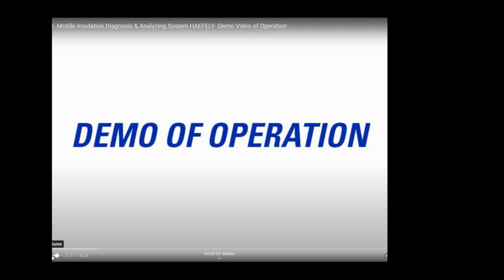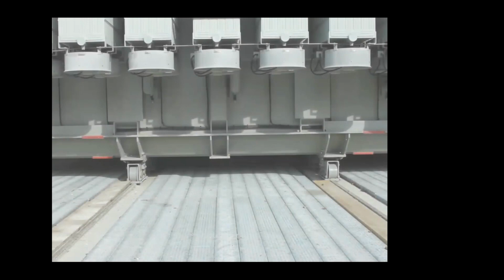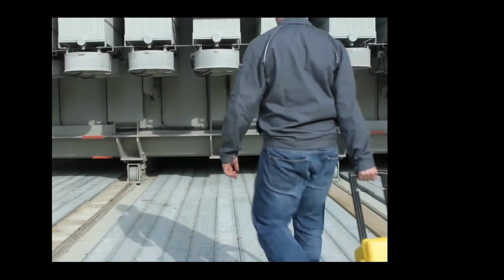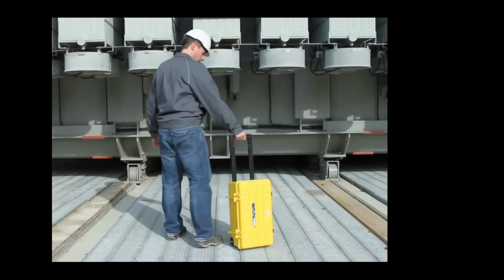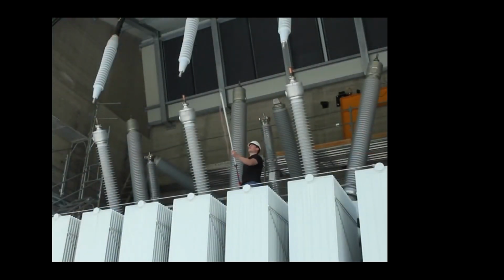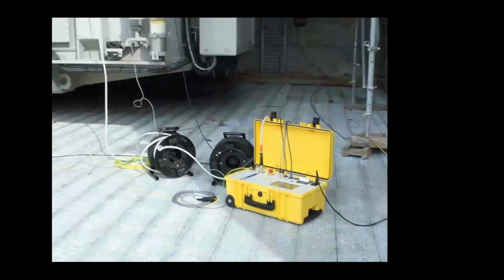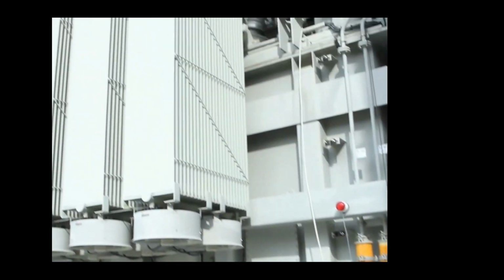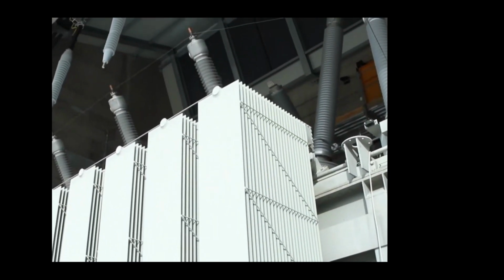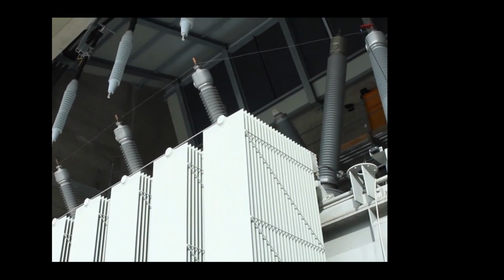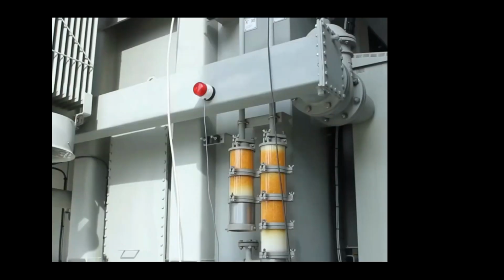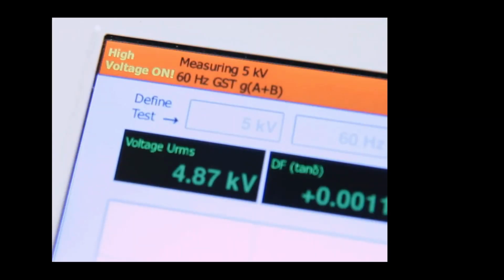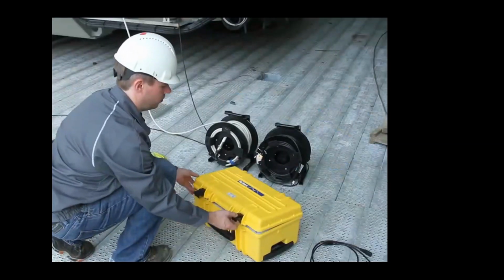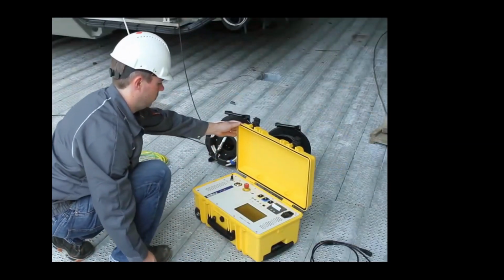We will walk through a detailed demo of operation for the MIDAS Micro. In this video, we will test a 2-winding transformer. All tests must be performed with the DUT completely de-energized and isolated from its power system. Testing will involve energizing the DUT through the MIDAS Micro, which can produce dangerous and life-threatening voltages and current levels. Extreme care and safety measures must be taken to avoid contact with the DUT and MIDAS Micro connections during testing.